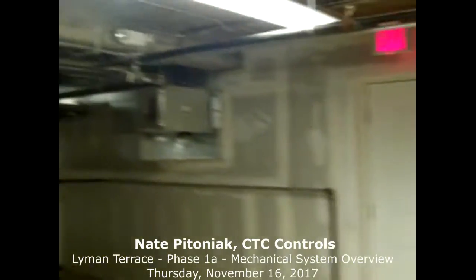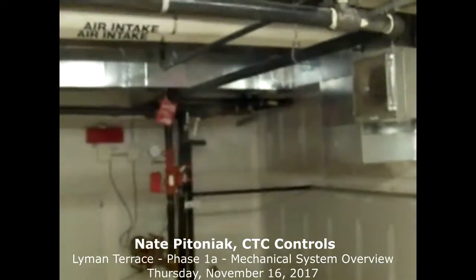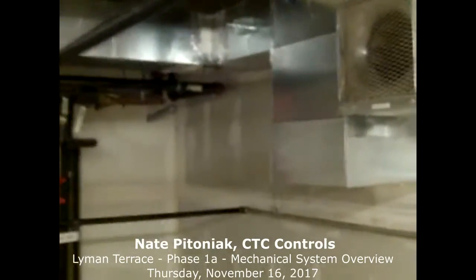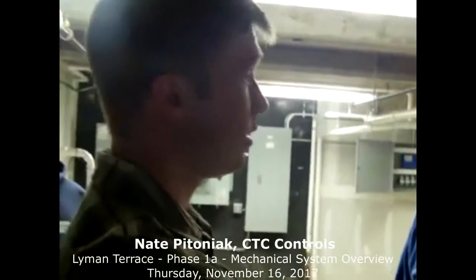In all your mech rooms, you have wall mount exhaust fans. Each has its own thermostat. When do those come on? Whenever it's warm in here. The reverse acting thermostat right now is set to 70. Anytime we're above 70 in here, it'll come on. We turn it down, now anytime it's above 55 in here. I did turn the switch off, just because it was loud and I couldn't hear anything, so someone must have turned it back on. Me.